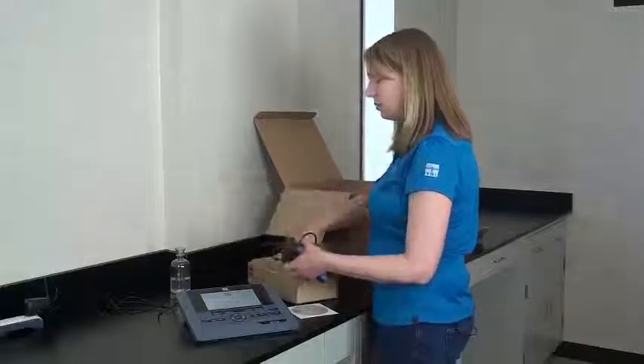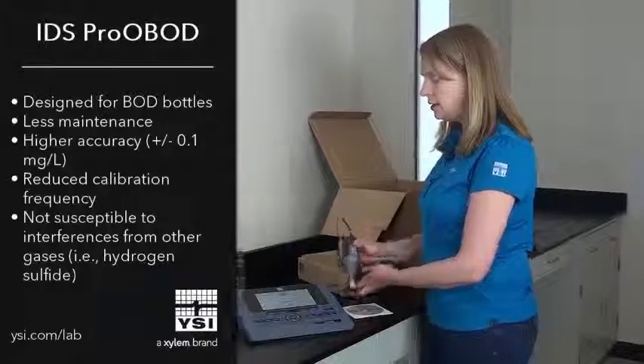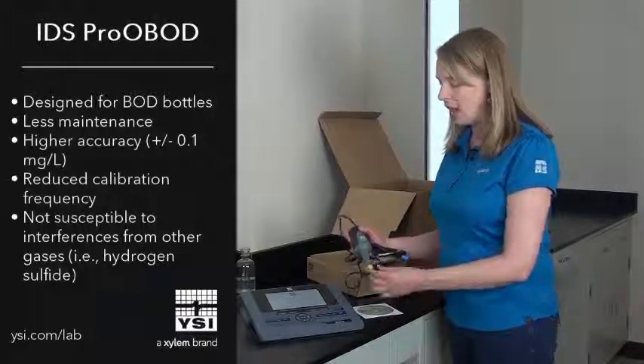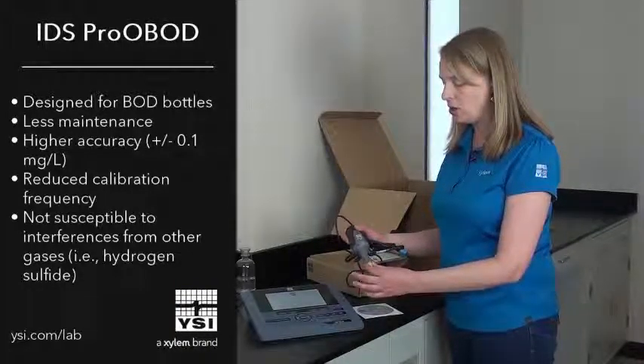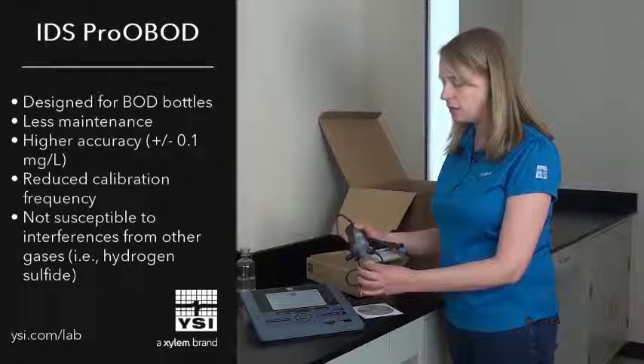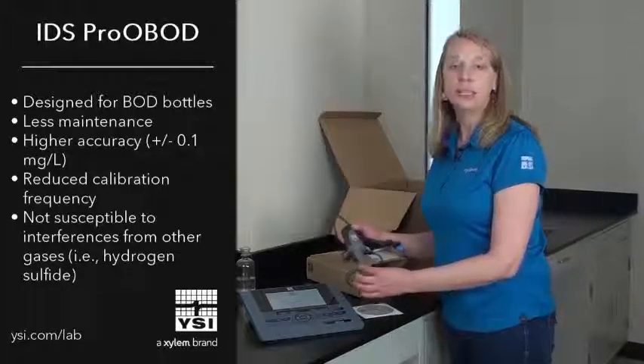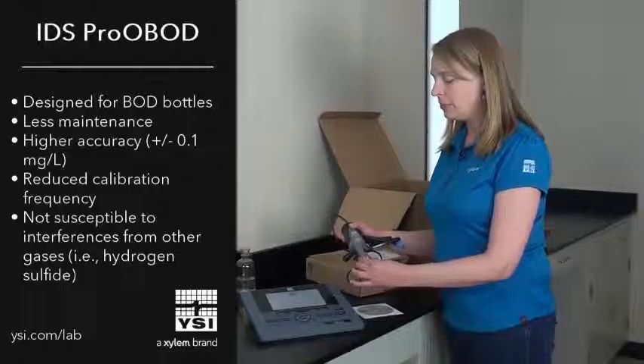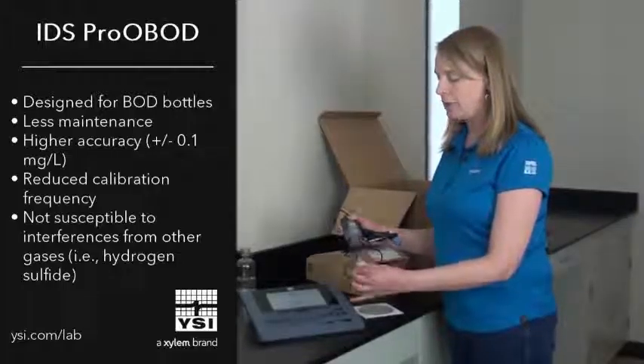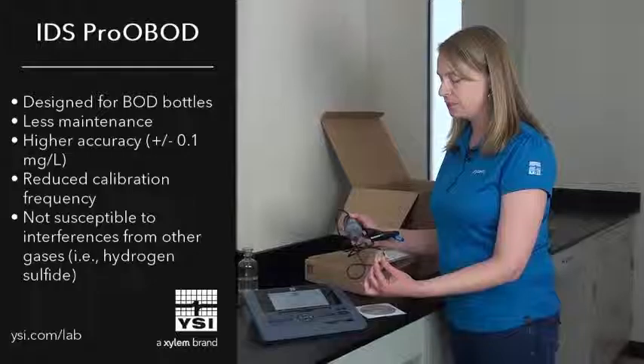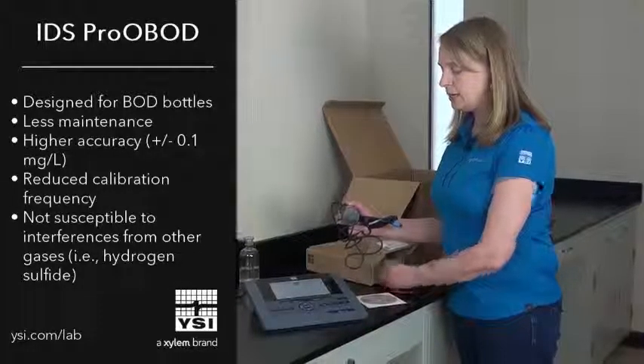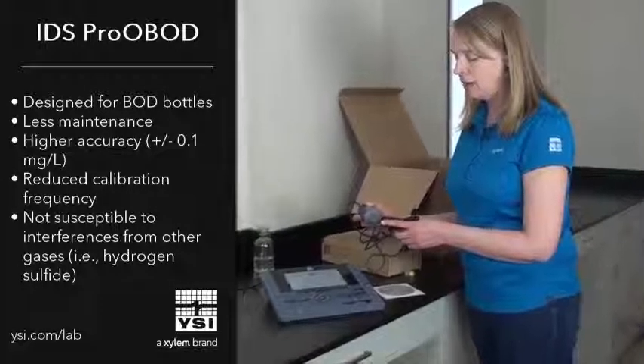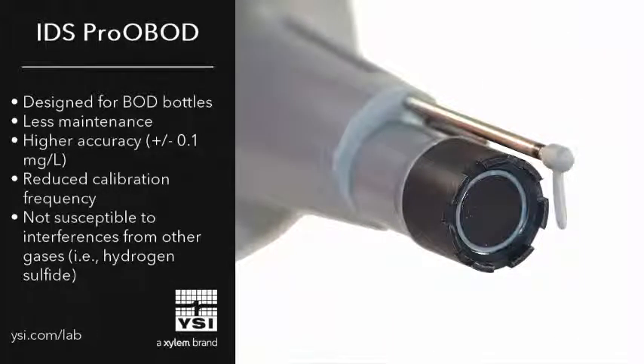We're going to demonstrate the ProOBOD today. The OBOD is the optical-based dissolved oxygen probe designed to fit in a BOD bottle. To get the OBOD up and running, simply remove the storage cap from the bottom of the probe. You can see that the guarded cap here is a little bit different than the traditional membrane that's used on previous versions of dissolved oxygen sensors.